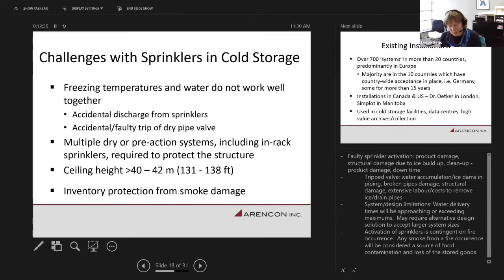You have to unload the freezer, you have to bring it up to temperature, or you have to heat the pipes. So for restoration of sprinkler systems, we've heard of systems where they have been frozen up for years without being addressed. So basically, I think a faulty operation could lead to an unprotected space. We have challenges just with the size of the systems. We need a lot more intervention because of the capacity limits.